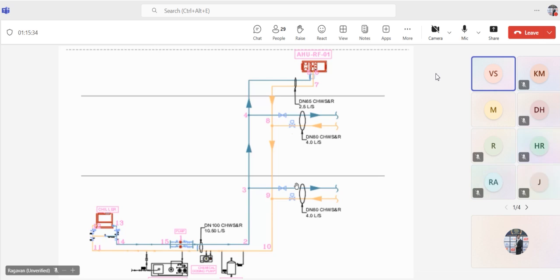If it is very difficult to do this for each and every pipe, because manual calculation takes too much time, that's the reason we have the flow chart. There is a range. For example, for a 2-inch pipe you have 20 GPM to 30 GPM, something like this, in the flow chart, so you can easily take that. Or if that is difficult, you do the calculation one by one, pipe size by pipe size, manually. It will take much more time compared to the flow chart. But the very important thing is the velocity of 1.5 meter per second.